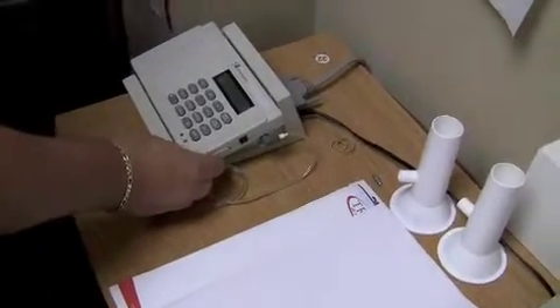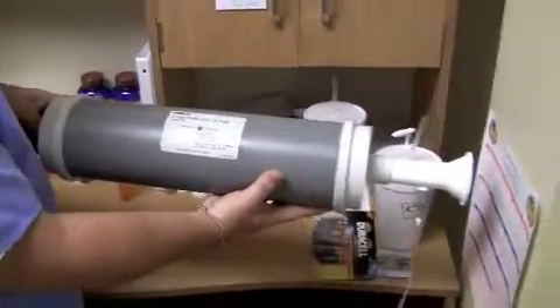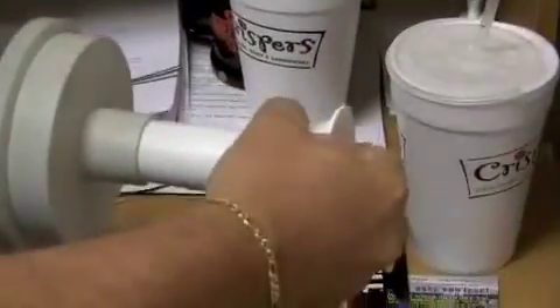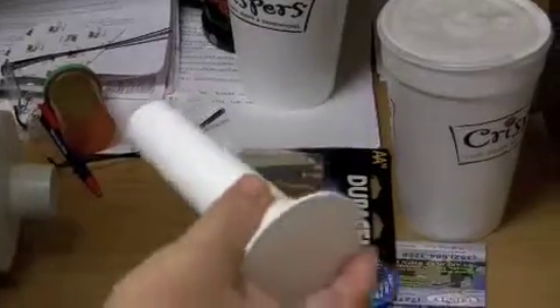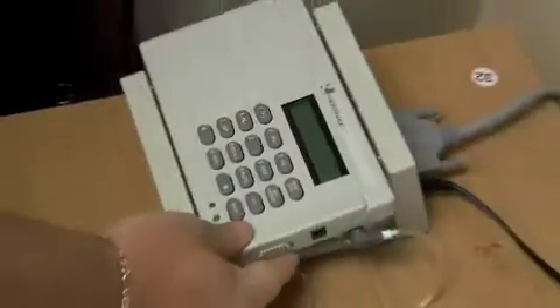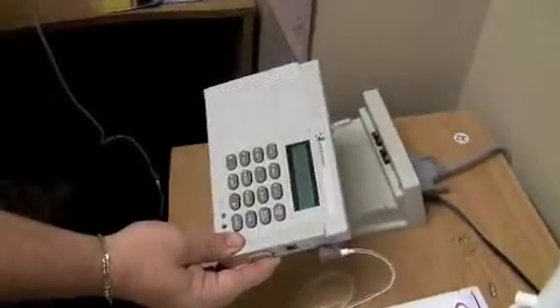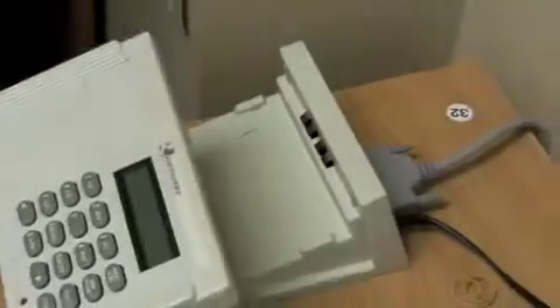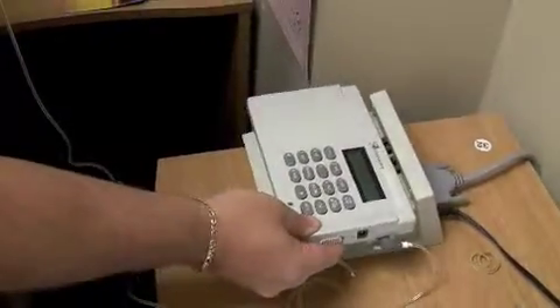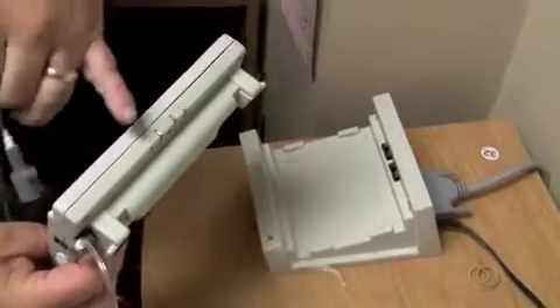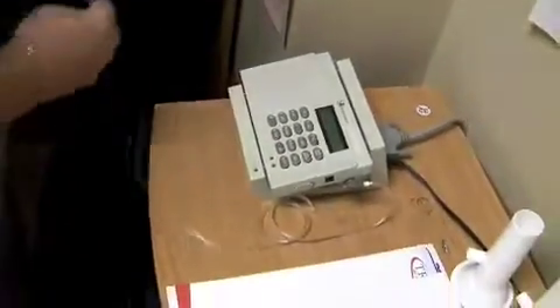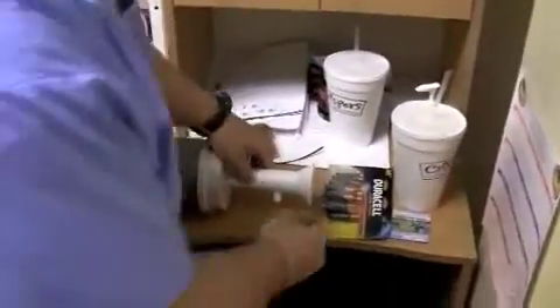machine. The first thing we want to go over is the product itself. What we have here is the calibration syringe or the calibration chamber. This on the end here is the mouthpiece, which detaches, and there is the line that goes into the actual machine itself. The base unit can be removed, so if you have to go into an exam room to do a PFT, this can be done very easily. But keep in mind, doing the calibration and doing the printout on the paper, the base has to be locked into the home base. There are little receptacles here that have to line up with the home base for it to work. Make sure that it's in properly, and at this point the calibration can begin.